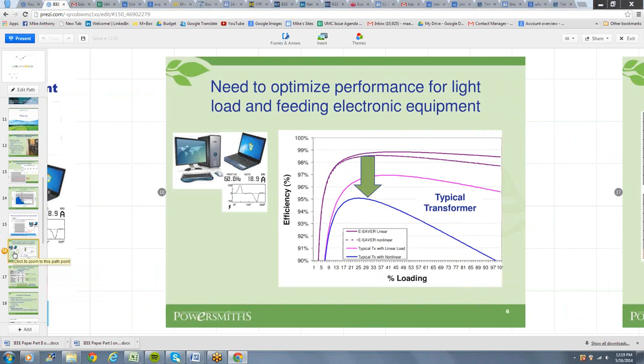So the next slide shows what the impact of that is from an efficiency perspective. The bottom pair of curves are the linear load in purple, and the nonlinear load in blue. As you can see, first of all, the efficiency at low load is low, but you can see quite a large gap as that load profile has changed from a linear ideal sine wave load down to the nonlinear load reality which we're feeding in real life.